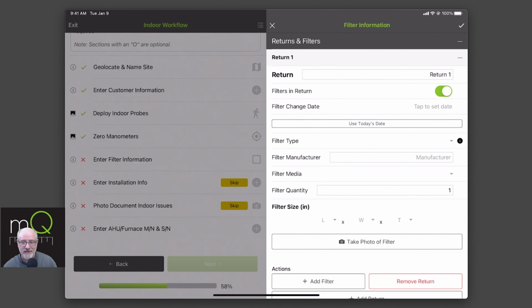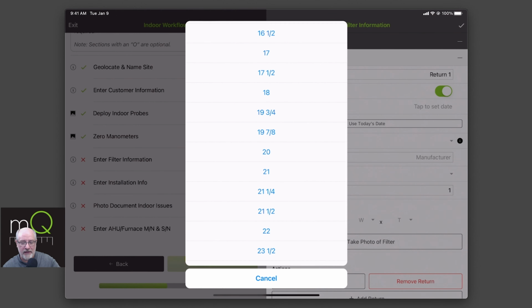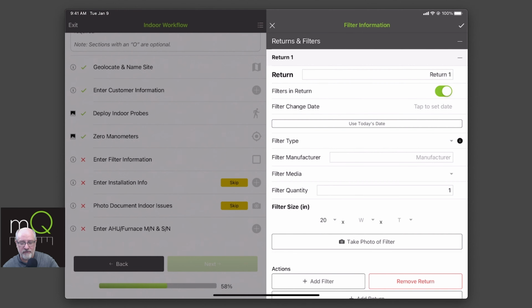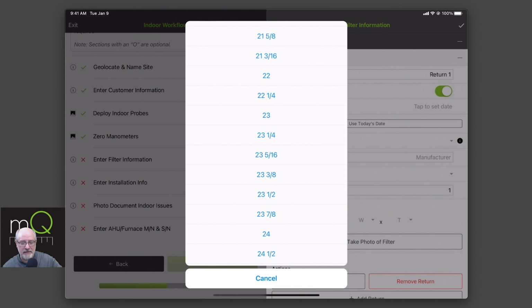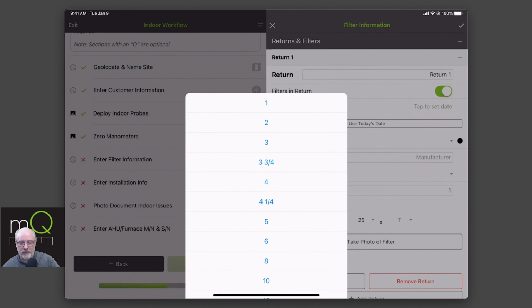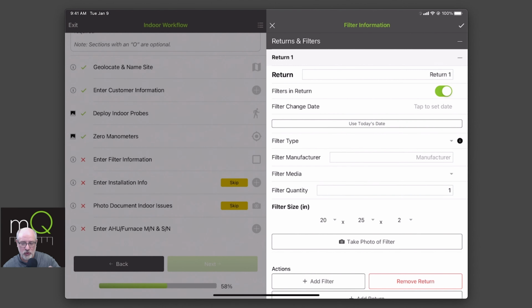So you must enter the size. We use the size to do filter face velocity - that's part of our vital score. If you have too small of a filter, not a depth, but the actual surface size, that's what we're calculating. So I need to enter some information here. We're going to go with a 20 by 25, and hopefully we're past the 1-inch filter now, so maybe we got a 2-inch.